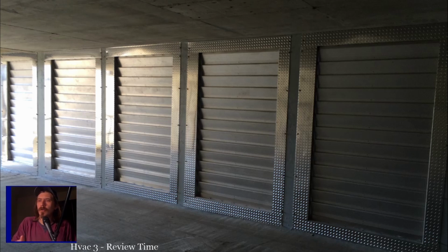You don't let the furnace kick on. You use the heat pump until it gets below a certain temperature, and then you let the furnace kick on. We still do it a lot with boilers. You'll use outdoor temp sensors to do outdoor reset on boilers, right? But back in the day, if you did higher end houses with multiple stages, the guys used to use outdoor thermostats all the time to control the stages to try and save energy on a system. And that's how you do it. There are still instances in which that's a good way to control electric heat to stage it.